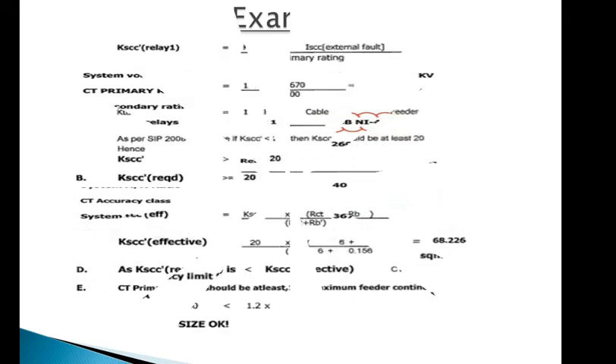Here the value of transient dimensioning factor (K_td) is provided by the CT manufacturer. In this calculation, since the required effective symmetrical short circuit factor is less than the calculated value, the CT size is OK and it will not mal-operate in this zone of operation.